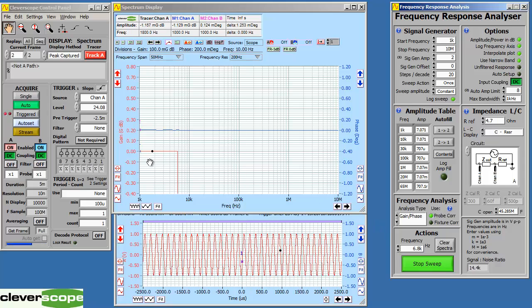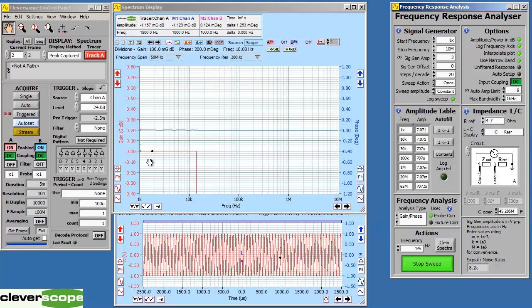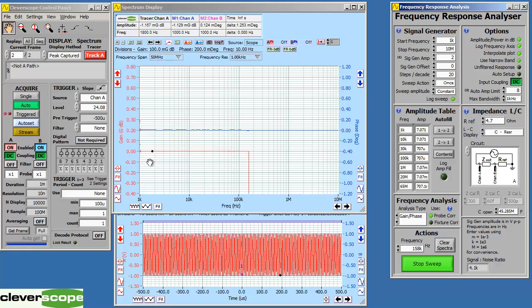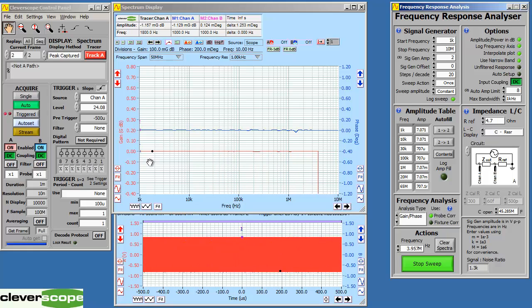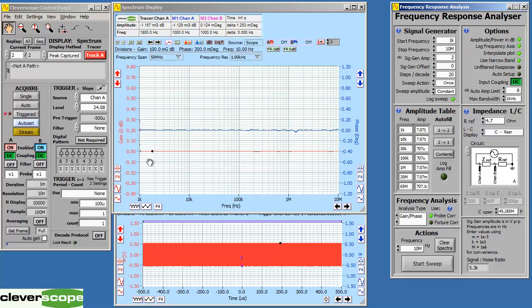As you can see, the gain response is now flat. Quite a lot better than plus or minus 0.01 dB. The phase response is also quite flat, with a much better response than the uncorrected probes. By using the probe correction system, you can attain maximum accuracy in all the measurements you do using the FRA. We commend it to you.